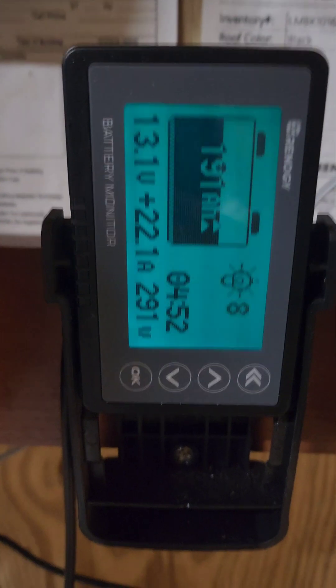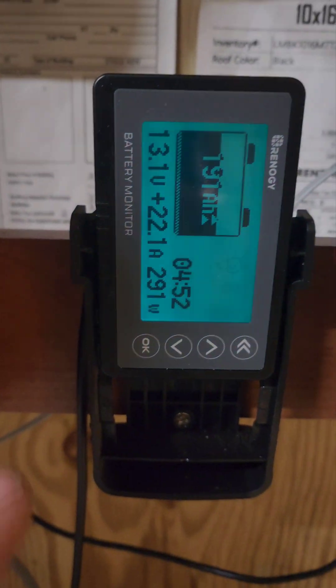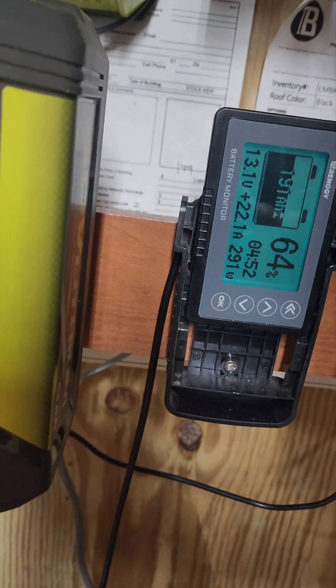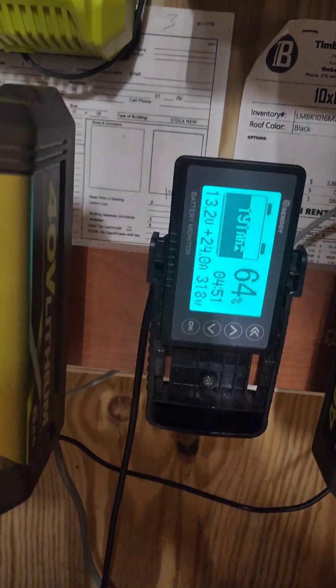Coming up to the monitor — there we go. We're putting in 22 amps. I'll kick off the loads. Into the batteries we're putting a total of 291 watts at 22.1 amps. It's saying we should be fully charged in four hours and three minutes, of course if we're not running any loads.